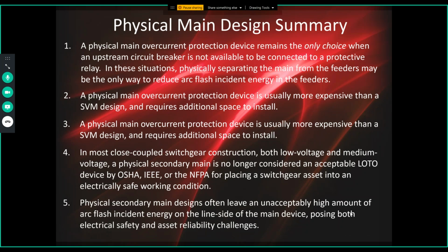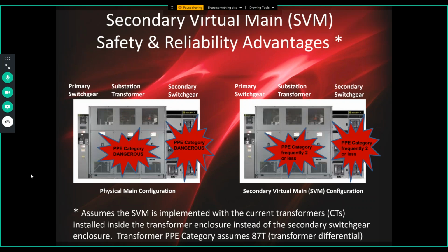And then the last point to consider, the fifth point, is that physical secondary mains usually leave an unacceptably high amount of arc flash incident energy on the line side of the main device, which poses both safety and system stability, reliability challenges. So when we compare a secondary virtual main and its safety and reliability advantages, I want you to look on both the left and the right. On the left, we have a physical main configuration, and on the right, a secondary virtual main.